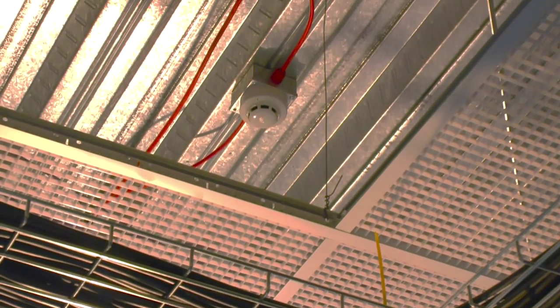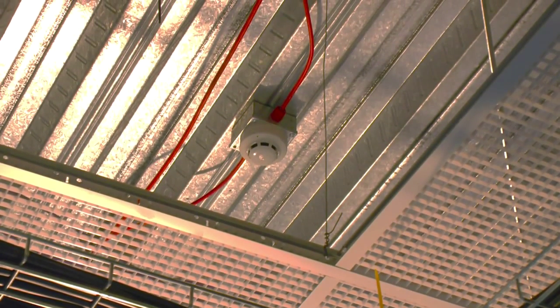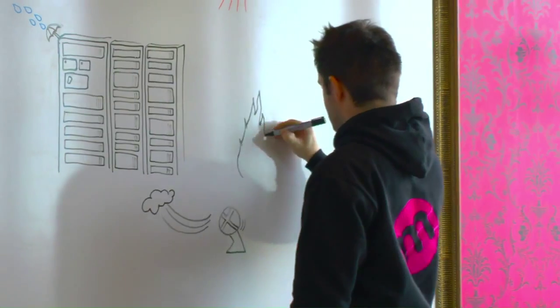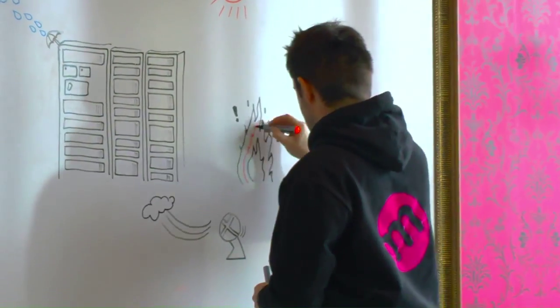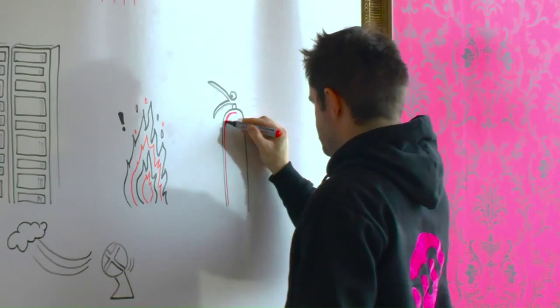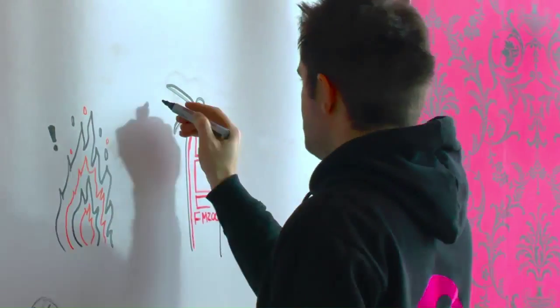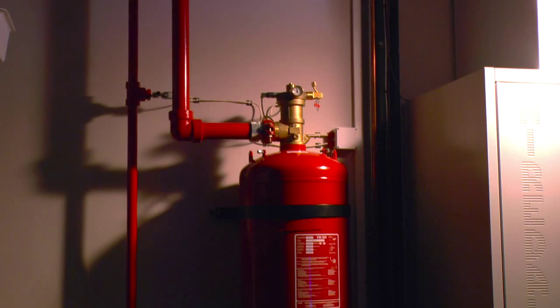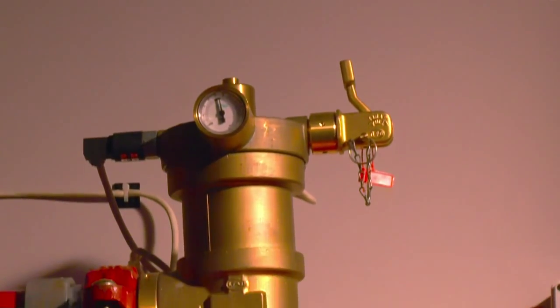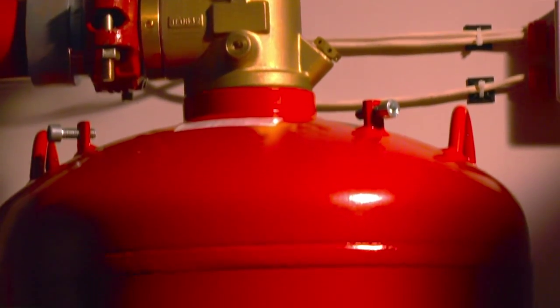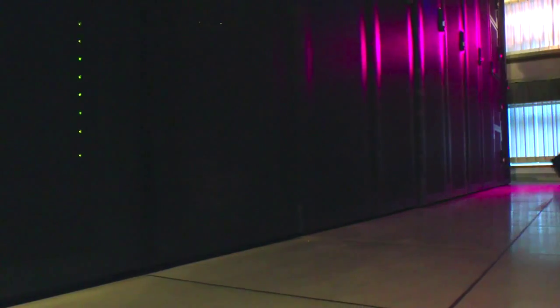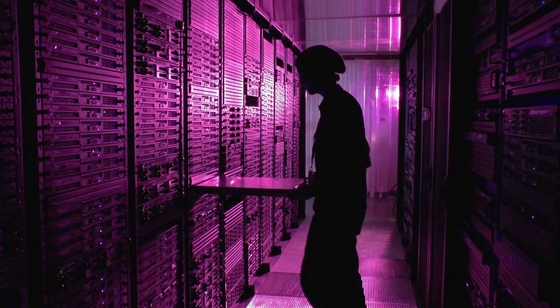Secondly, as a backup, we have conventional smoke detectors at ceiling level and below the floor. If a fire does break out, after 30 seconds, FM200 gas is released into the air from the fire suppression system. This high-tech gas works by removing the heat energy from a fire and lowering the oxygen content in the room. The whole system is designed to be completely safe to humans, whilst being able to deal with a fire without having to switch off the power to your servers.